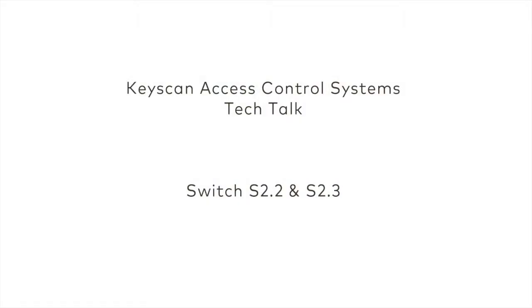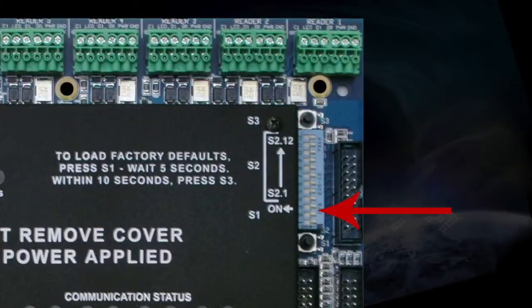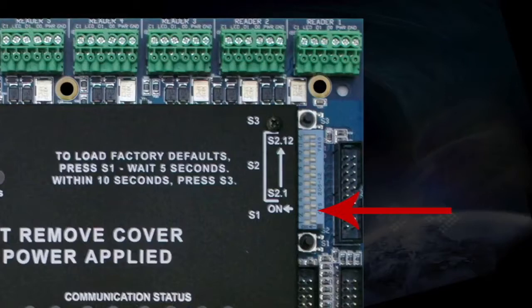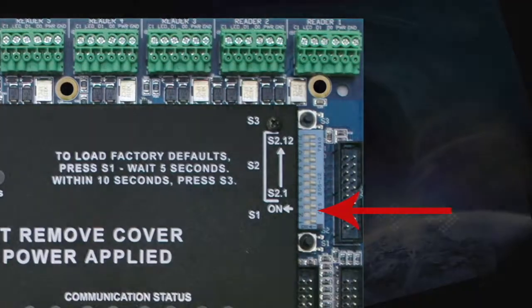Switch 2 and Switch 3 control the communication baud rate of your access control unit. The default baud rate is set to 57.6 kilobits per second. You may need to change this baud rate if you're retrofitting the unit to an existing Keyscan installation that may not support this rate. You can also increase the baud rate to 115.2 kilobits per second when the unit is equipped with an onboard NetCom 2P, providing faster communication for faster uploads.